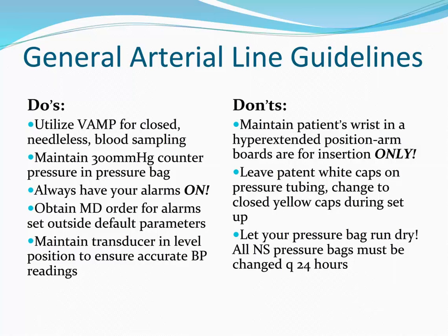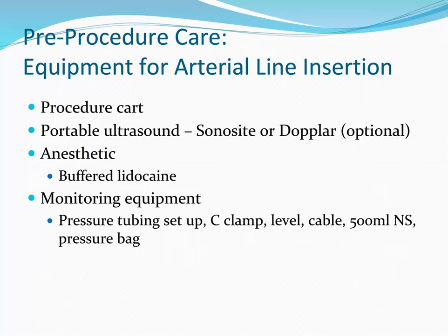Don't let your pressure bag run dry. If you're changing this every 24 hours, it is unlikely that it will run dry. When the bag is maintained at 300 millimeters of mercury, it will infuse 3 milliliters of volume an hour to maintain line patency.